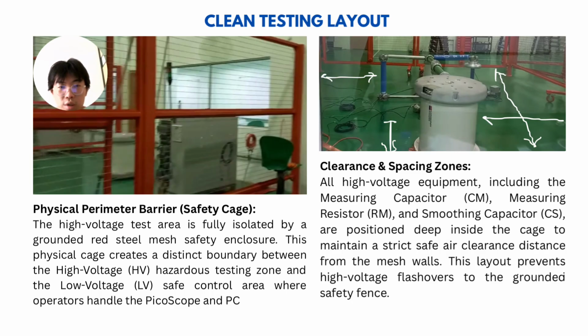And the next is the clearance and spacing zone. All high voltage equipment, including the measuring capacitor, measuring resistor, and smoothing capacitor, are positioned deep inside the cage to maintain a strict, safe air clearance distance from the mesh wall. This layout prevents high voltage flashover to the grounded safety fence.